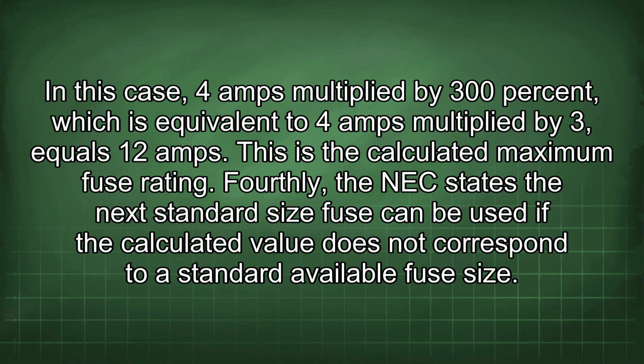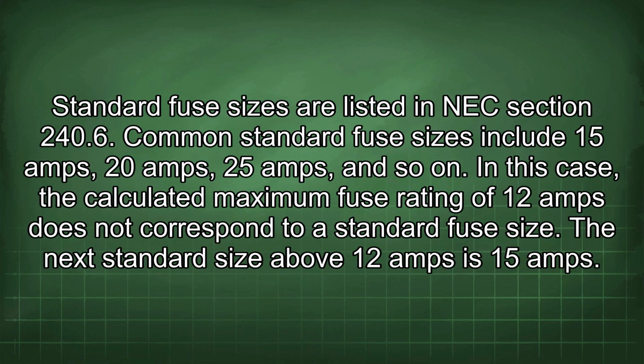Fourthly, the NEC states the next standard size fuse can be used if the calculated value does not correspond to a standard available fuse size. Standard fuse sizes are listed in NEC section 240.6. Common standard fuse sizes include 15 amps, 20 amps, 25 amps, and so on. In this case, the calculated maximum fuse rating of 12 amps does not correspond to a standard fuse size. The next standard size above 12 amps is 15 amps.